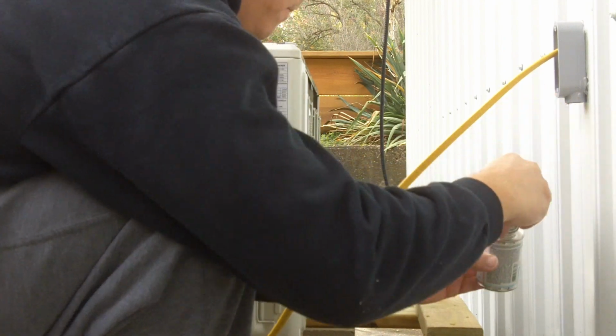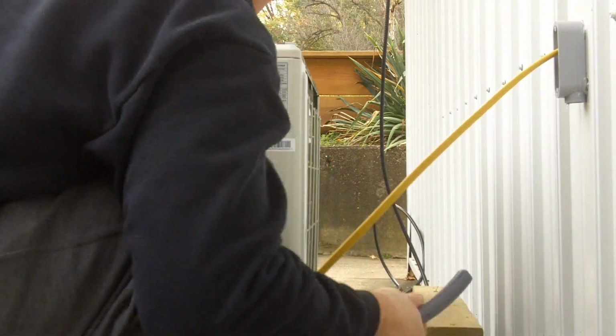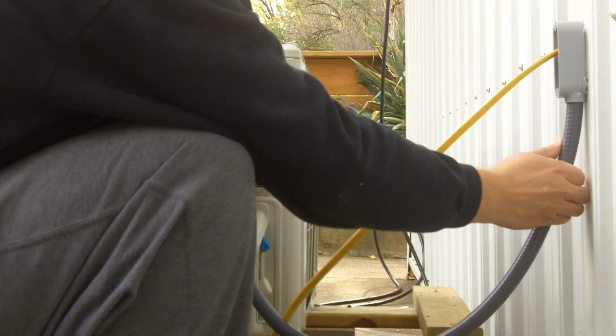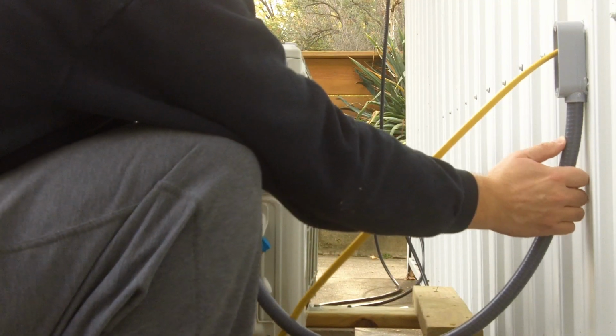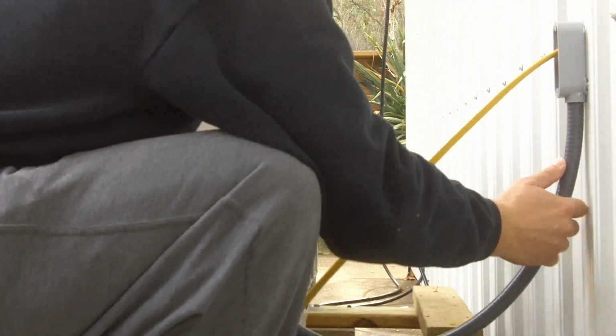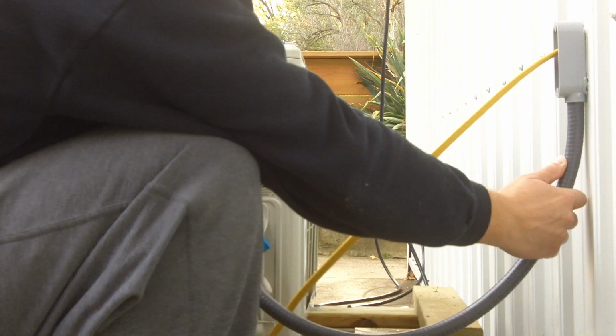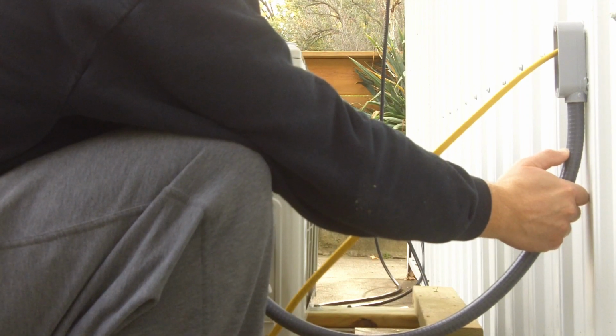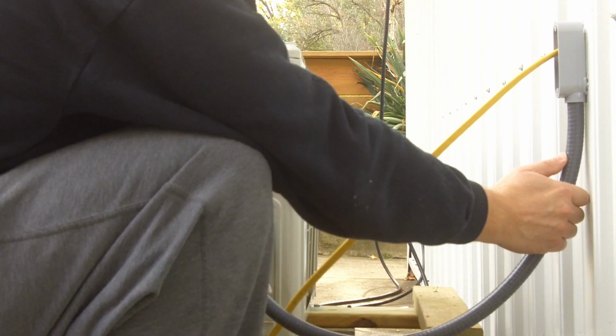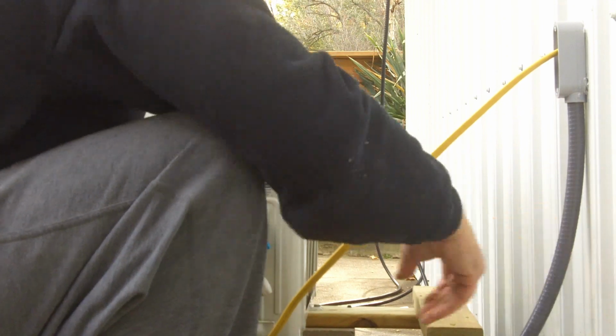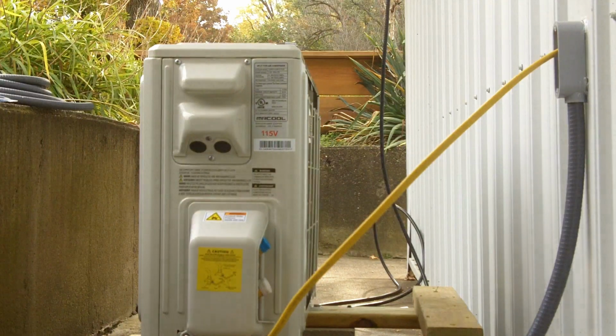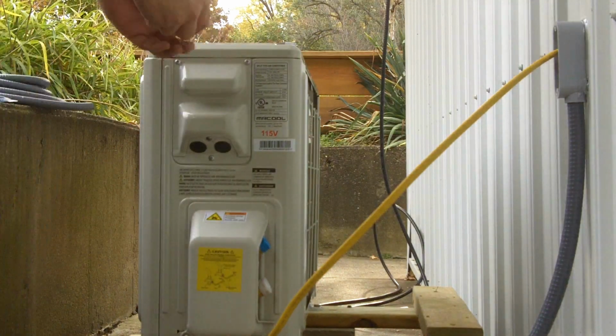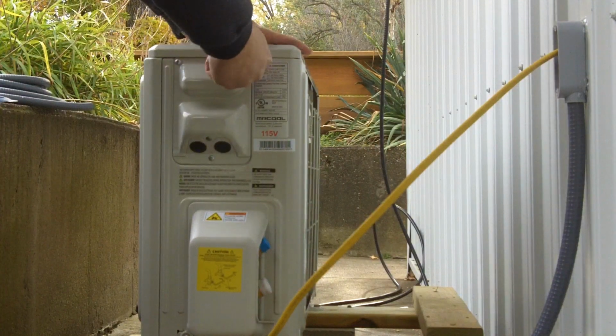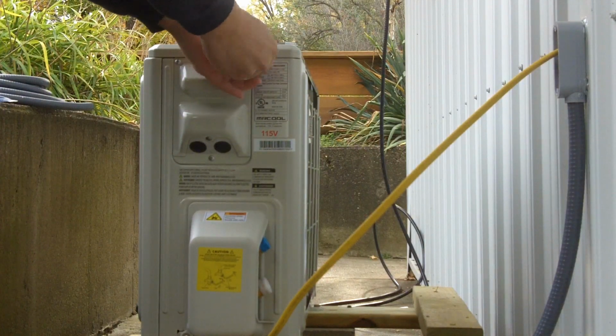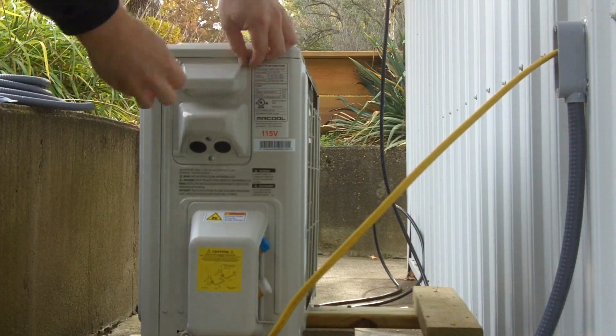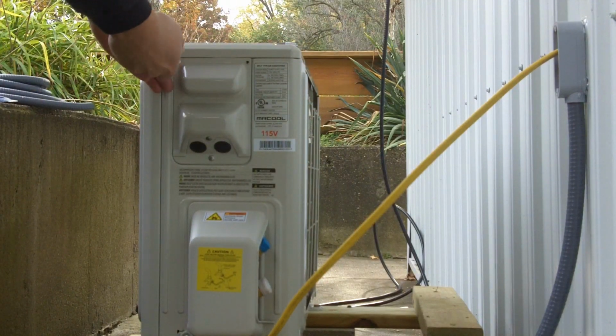It's very cramped in there. You have the black cable coming from the indoor unit to the outdoor unit, and you have to get all those wires into this little contained area with the 12 gauge, which is thicker and harder to bend than 14 gauge wire. So you've got a stout feed coming in with 4 lines - 3 lines plus a ground wire from the indoor unit - so you'll have 7 wires inside this small area. You have to pre-bend all your wires and get everything lined up.